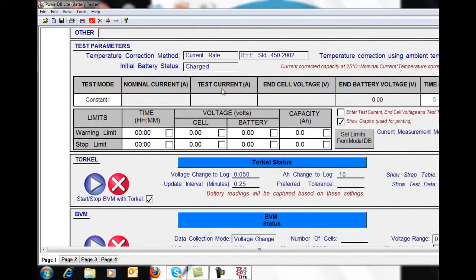The type of test I'm going to run is a constant current discharge test in accordance with the IEEE standard 450. By checking this box over here, I can enter in test current and end voltage levels. So again, I'm going to run a constant current test, although I could run constant resistance or constant power. I can program in a custom current profile or power profile if I was doing, for instance, a UPS bank. I'm going to leave it as constant current.